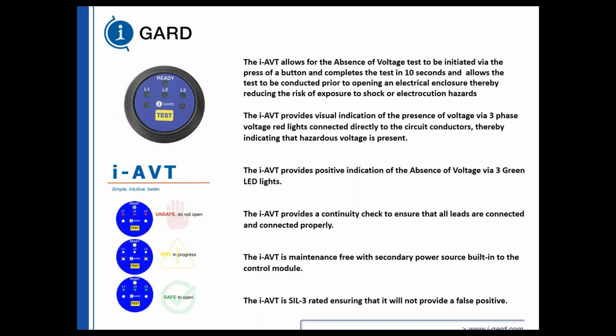Z462 in the 2021 version and NFPA 70E in the 2021 version understand that, and they've had to implement more safety related products suitable for the use of verifying the absence of voltage to remove people from harm's way when they're conducting the absence of voltage test the historical way.